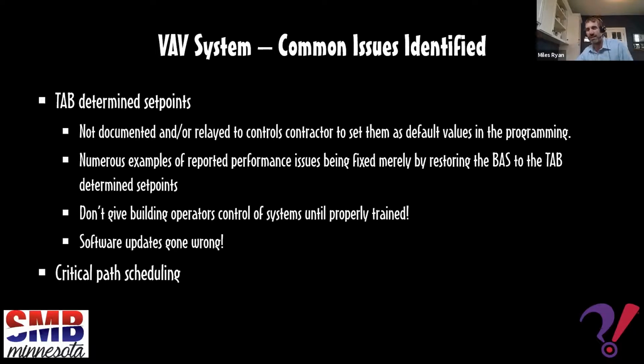And we do this because as the building moves into its occupancy phase, building operators, for various reasons, have to make adjustments to the system. Now, an unknowing building operator might make inappropriate adjustments to the system, and then a few years later, they have to bring in a consultant, a retro-commissioning team, to come in and get the building back up to snuff. And oftentimes what we find is the set points are drastically different than what they were set up to be. And sometimes we don't have the information to know exactly what those optimum set points were, because the TAB report was either never filed, or if it was filed, it didn't have that information clearly displayed.